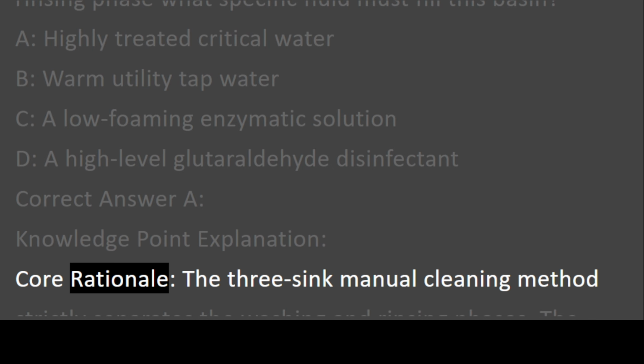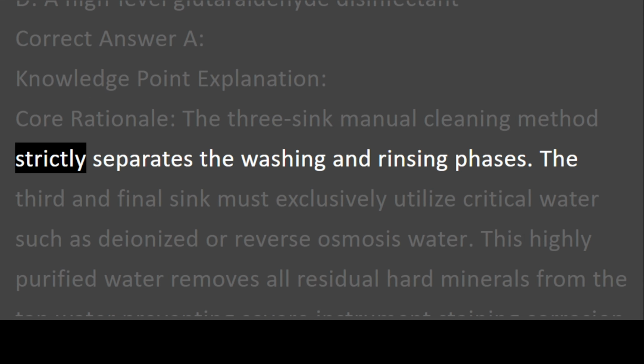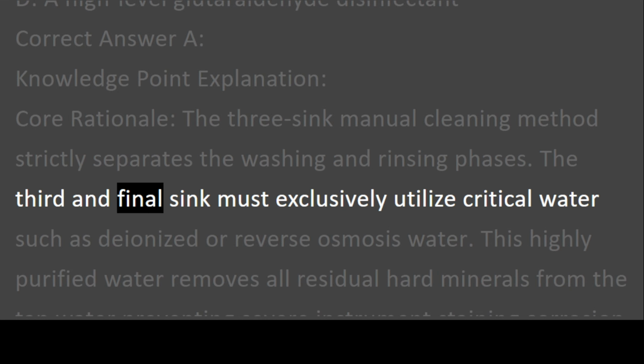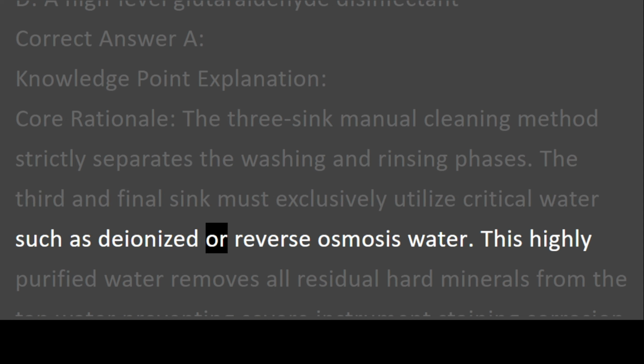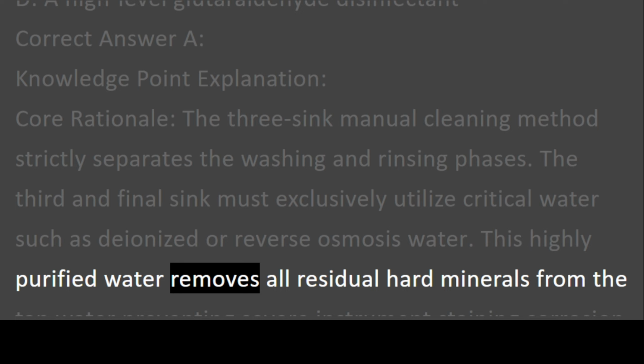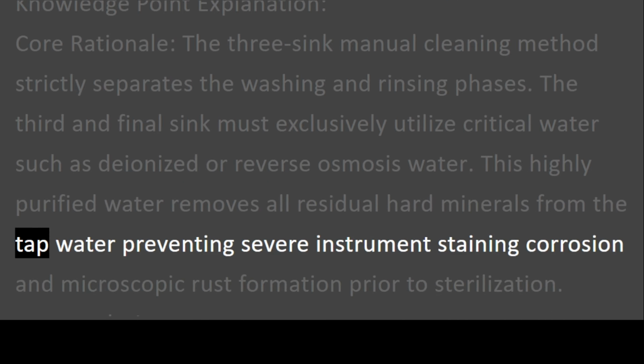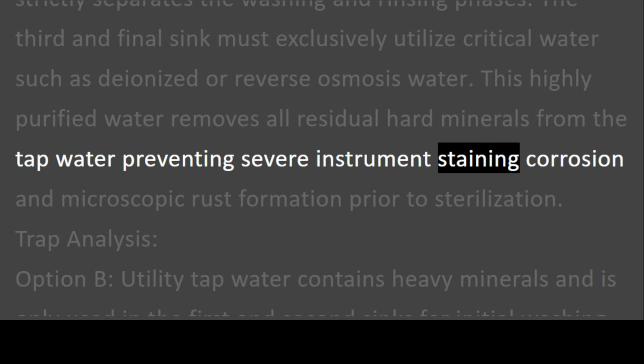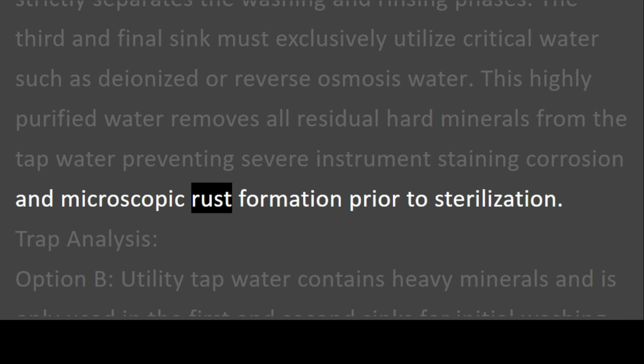Core rationale. The 3-sink manual cleaning method strictly separates the washing and rinsing phases. The third and final sink must exclusively utilize critical water such as deionized or reverse osmosis water. This highly purified water removes all residual hard minerals from the tap water, preventing severe instrument staining, corrosion, and microscopic rust formation prior to sterilization.